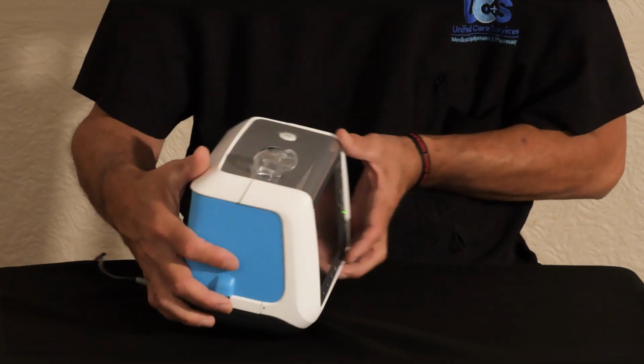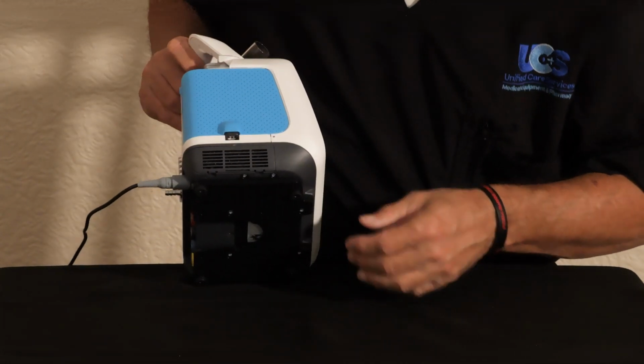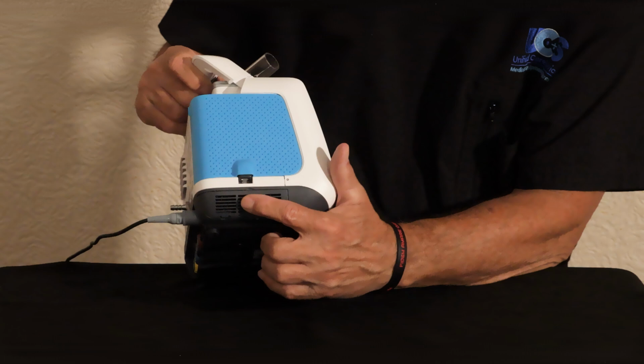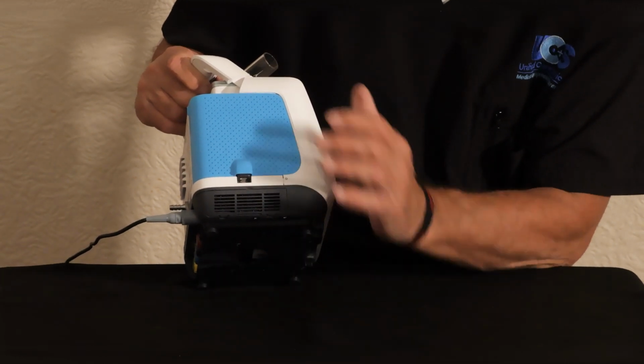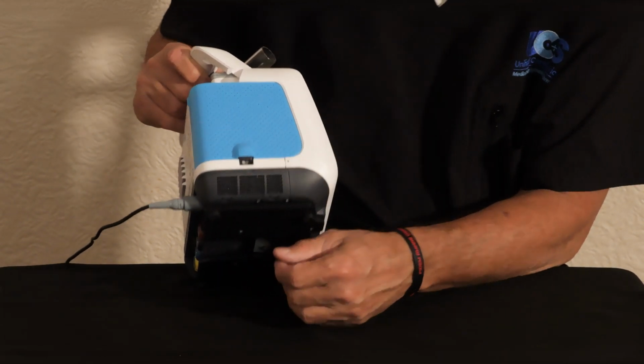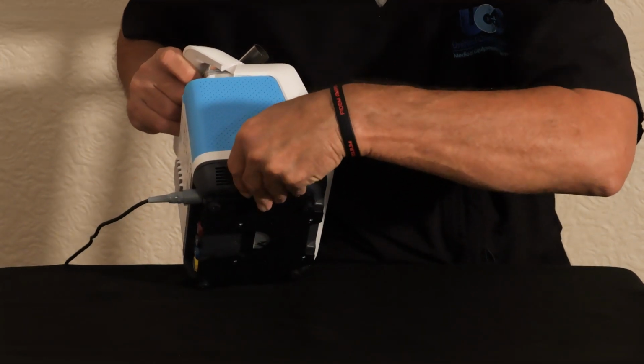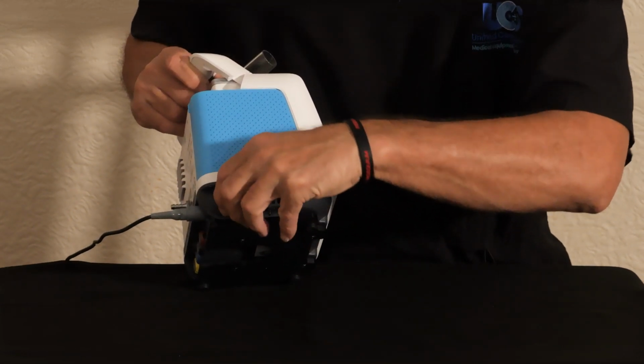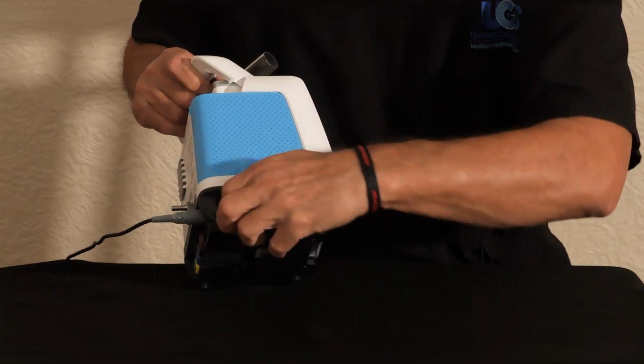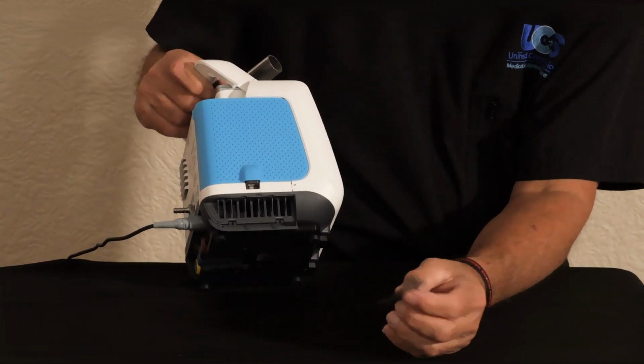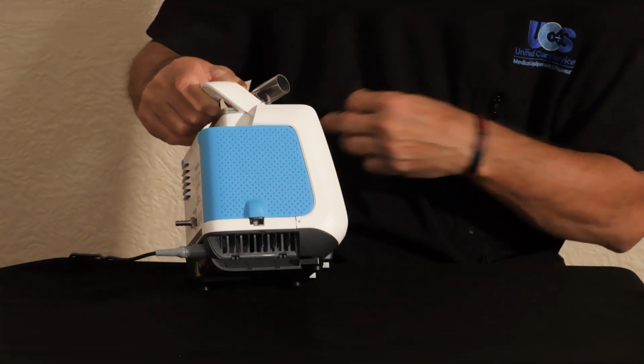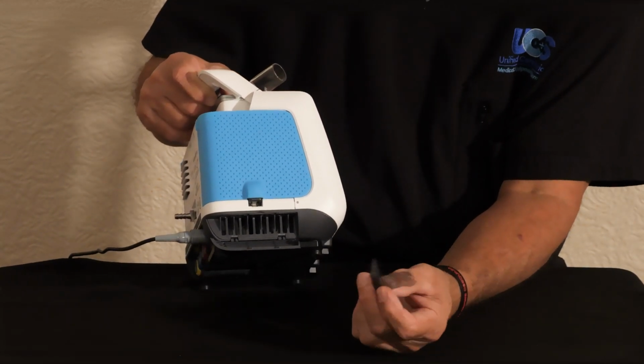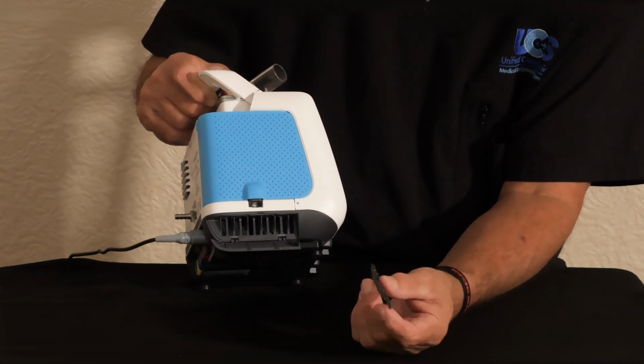Now, if you look over here, you have a fan inlet filter that basically, this is the fan that cools the motor inside the ventilator. This also has to be maintained. There's a little door here where it opens. This is also a non-disposable, reusable filter. So when you clean the filter on the other side, you're going to take this filter as well, wash it, dry it, and put it back. Get all the dust off.